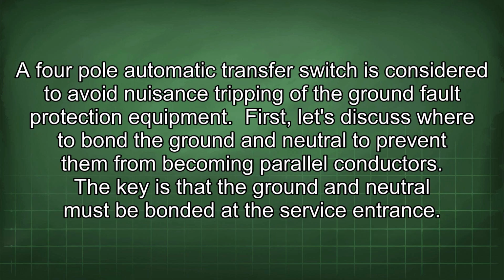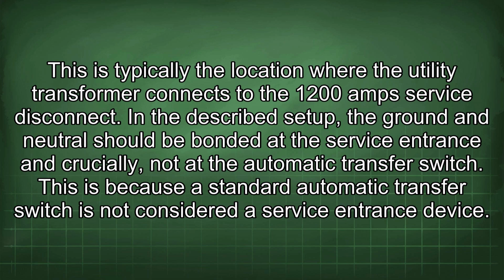A 4-pole automatic transfer switch is considered to avoid nuisance tripping of the ground fault protection equipment. First, let's discuss where to bond the ground and neutral to prevent them from becoming parallel conductors. The key is that the ground and neutral must be bonded at the service entrance. This is typically the location where the utility transformer connects to the 1200 amps service disconnect.